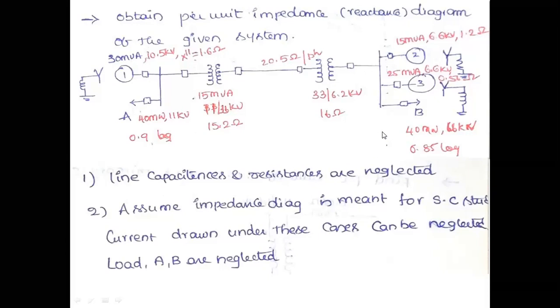Assume the impedance diagram is meant for short-circuit studies. Under these conditions load A and load B can be neglected. So directly, even though load A and load B are present in the single-line diagram, you do not consider those two loads, because the problem itself has mentioned that you have to avoid load A and load B. Except those two, you need to draw the per-unit impedance diagram, the reactance diagram, of this particular system.